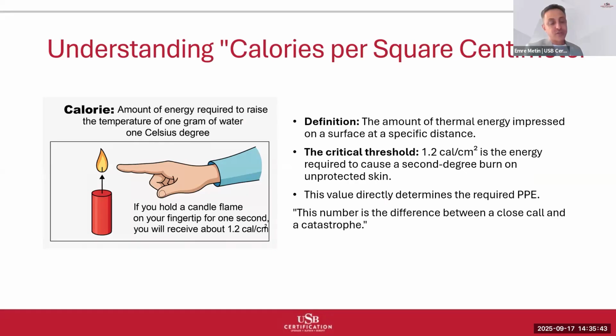Now, let's decode what those analysis results actually mean. The output of arc flash analysis is expressed in calories per square centimeter. But what does this really represent, and why is this particular unit so important? A calorie is a unit of energy, specifically the amount of energy required to raise the temperature of 1 gram of water by 1 degree Celsius. When we talk about calories per square centimeter, we are describing energy density, how much energy is delivered to each square centimeter of surface area.